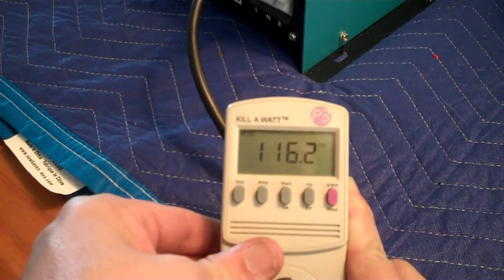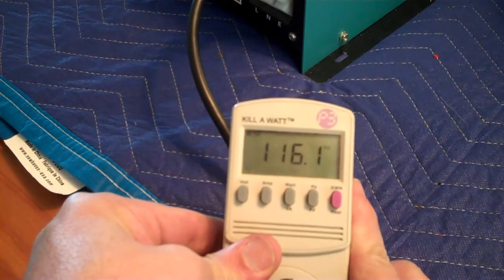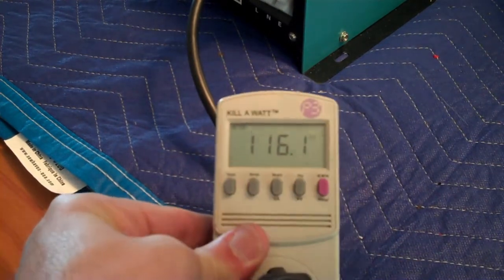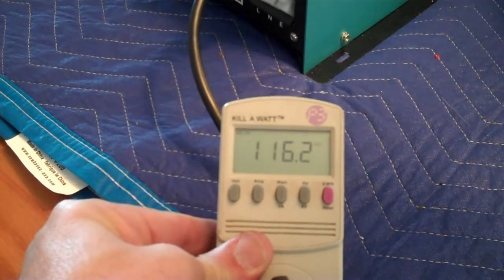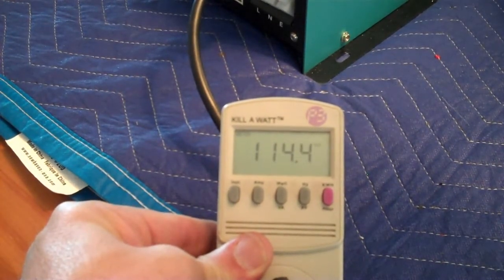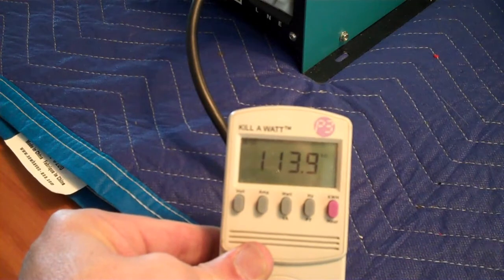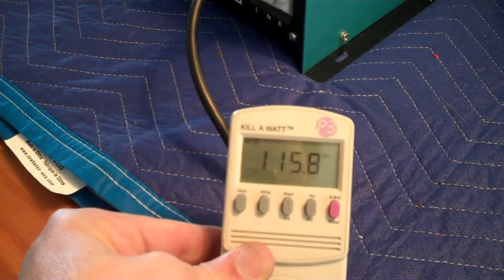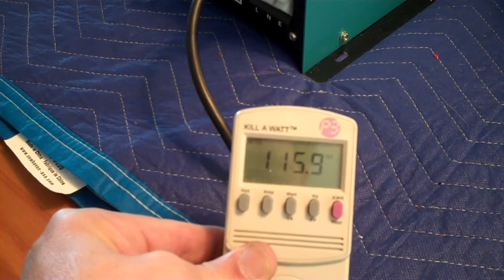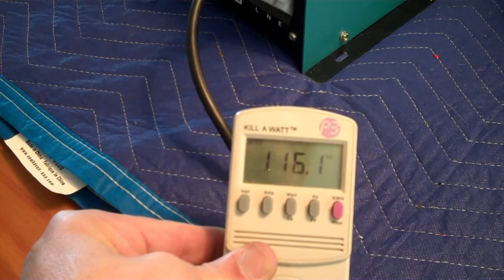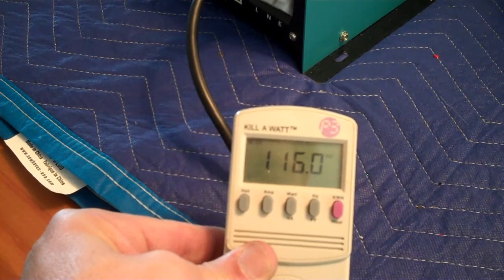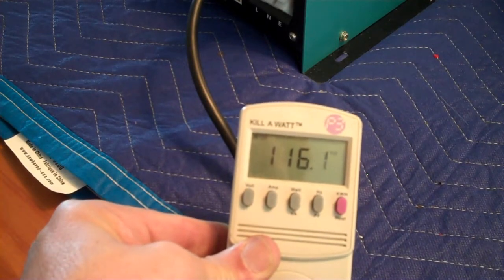Let's take a look at the voltage and see how much the voltage sags when this thing turns on. All right, so it sagged from about 116 idle down to 112, 113 when it first started up, and it was running at about 114, so only about a 2-volt sag. That's pretty good.